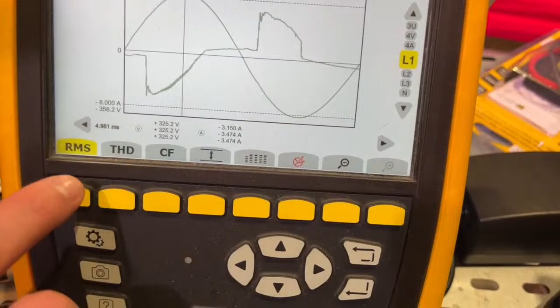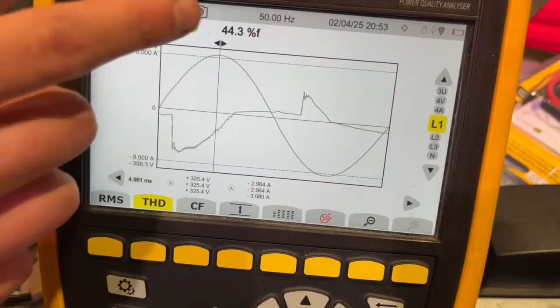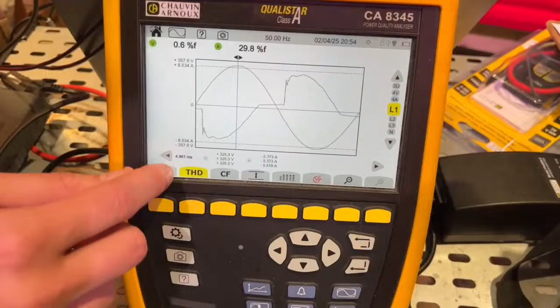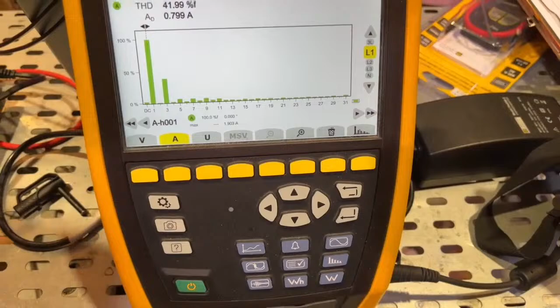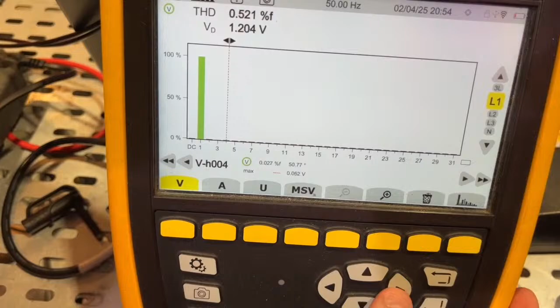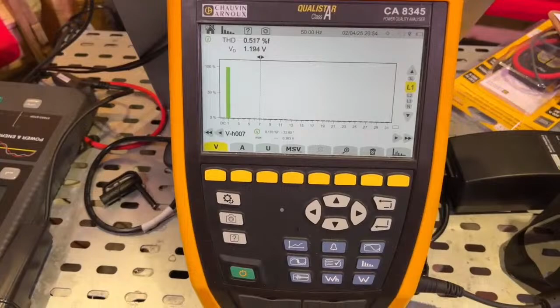And then what we've got over here are these soft keys, so any of these buttons at the bottom, we can press THD for instance, and we can see a THD value in comparison to the fundamental. Then we have crest factor, which I won't go too much over. And at the bottom here we have harmonics, so we can see what voltage harmonics are there, and go along at each current order. I'm on current at the moment, but we can go along and see, number one is our fundamental. So this is our voltage, the harmonics that we've got at the first, which is the fundamental, obviously 100%. And then we can see thereafter, and go all the way up to the 127th. It can log and do everything.